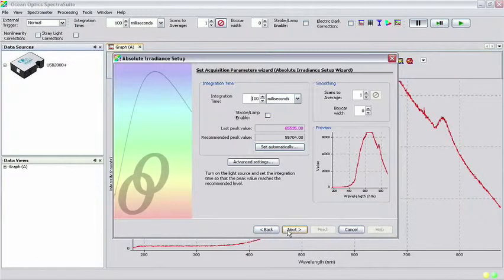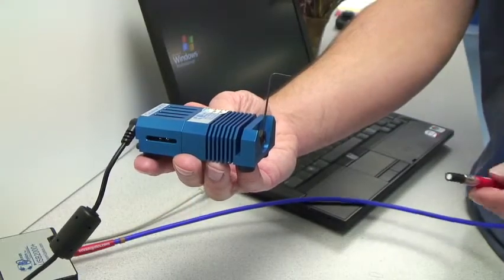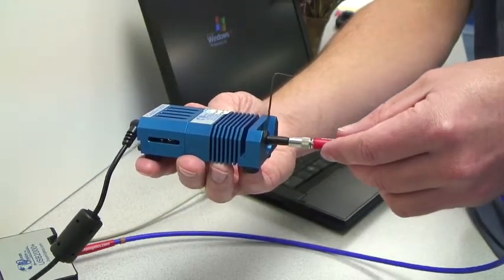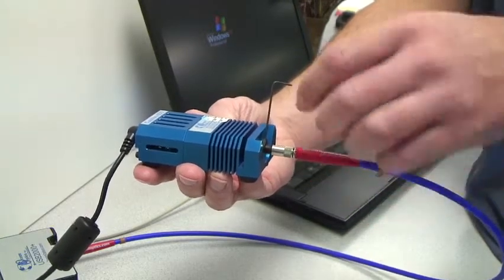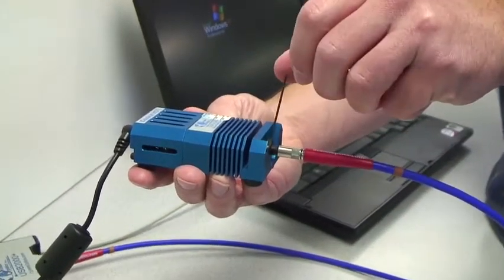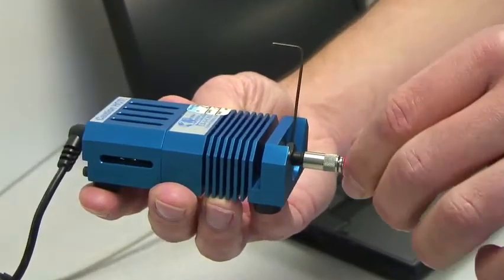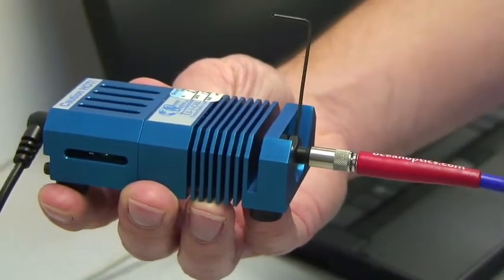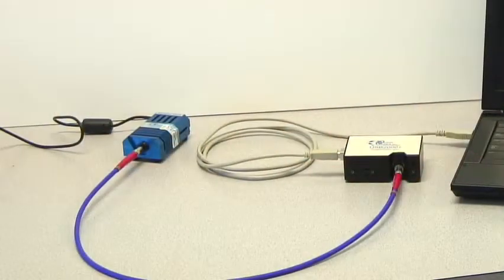Before we set the acquisition parameters, we need to place the bare fiber adapter into the LS1 Cal. Loosen the set screw and insert the bare fiber adapter into the port on the light source. Make sure that the bare fiber adapter slides all the way into the port on the light source, and then tighten the set screw.